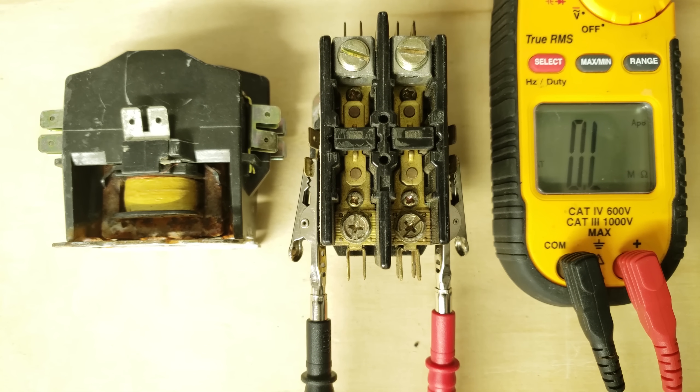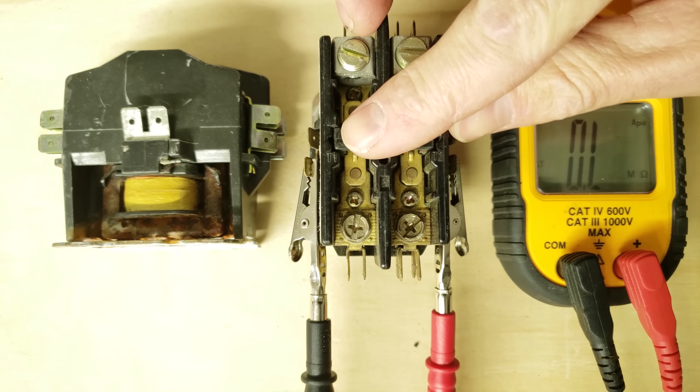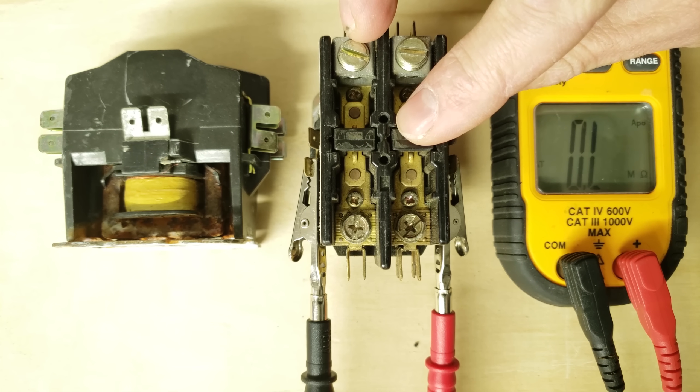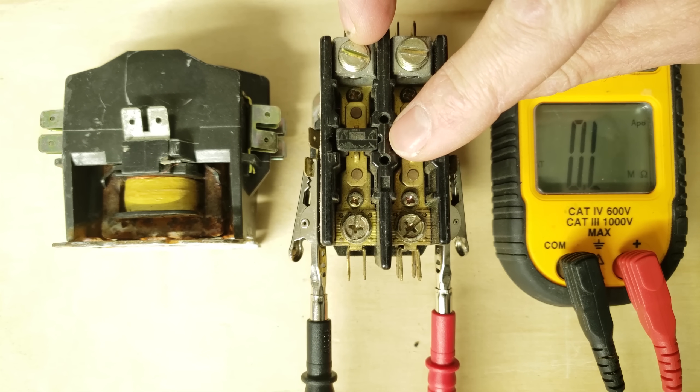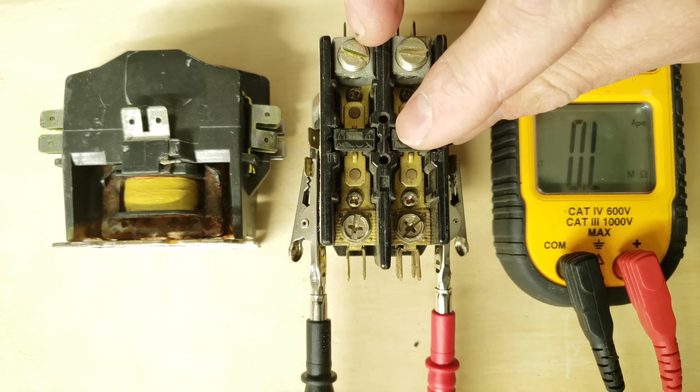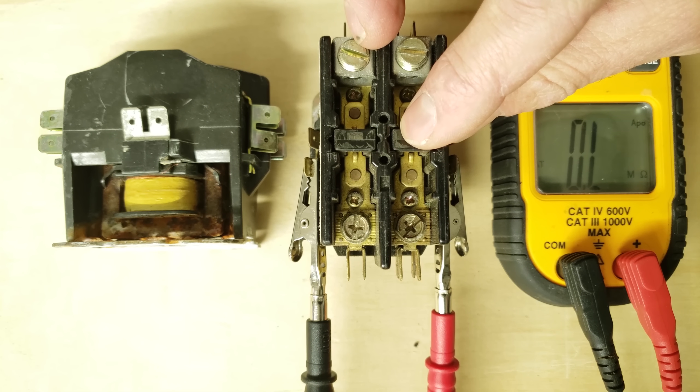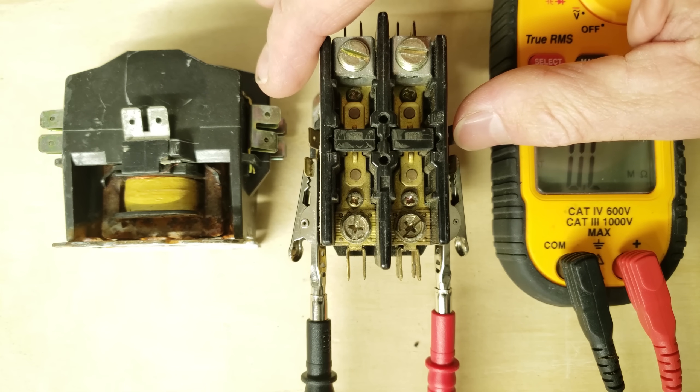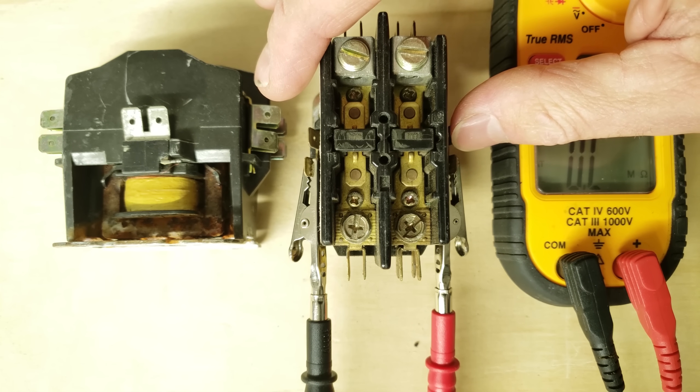You could have high amperage being drawn if these contacts were sucking only partially down. If they were hanging up due to an insect or the plastic is wearing and it's only pulling down part of the way, you're gonna draw a lot more amperage on the coil. The coil is a very small wire and that's gonna end up burning out.